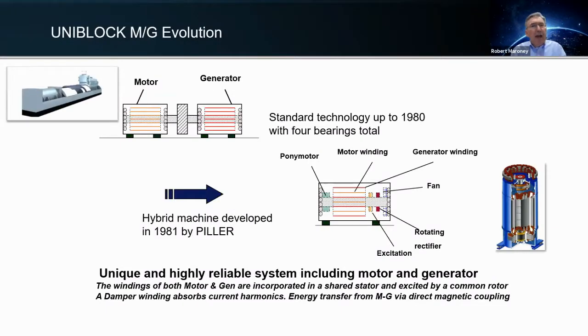So how do we do that, and how has it matured over the years? Well, in the old days, in the large mechanically connected systems, you actually had a separate motor that was shaft connected or mechanically connected to a generator. And you needed those two components, one to motor, to spin that machine while it's online on utility power. But it also needs to be able to generate current or reactive current for output to the load for voltage regulation.